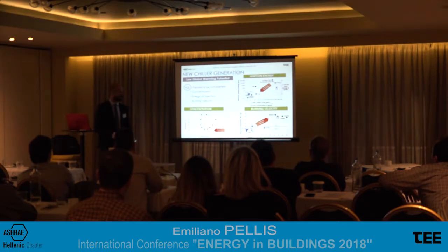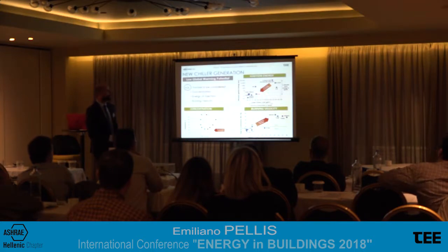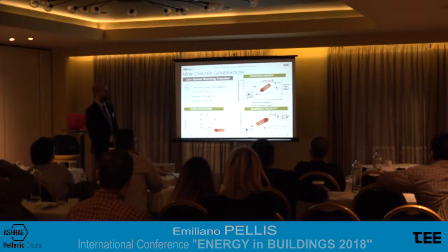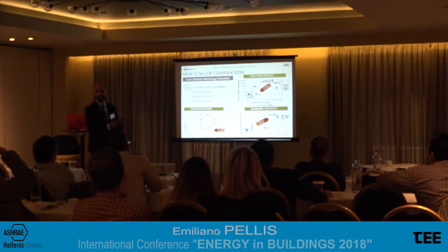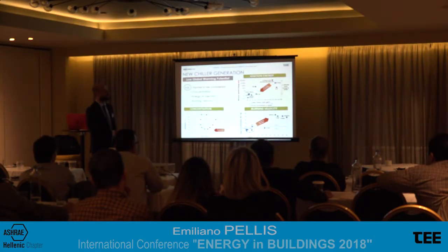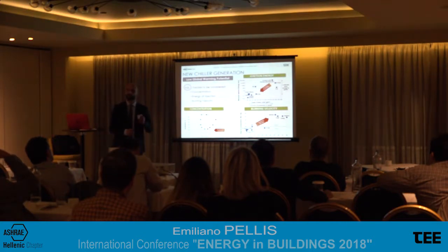When we talk about A2L class refrigerant, they are flammable only within a concentration range. Outside of this area, they are not flammable, exactly similar to A1 refrigerant. Second point, ignition energy. To ignite the refrigerant, we need some energy. If you look at the graph here, on the horizontal axis you have the ignition energy needed, and on the vertical axis here we have the ignition energy for the gasoline, which is something that all of us can easily identify as flammable. If we take one of the new refrigerants, for example this one, you see the ignition energy is definitely higher, more than 250,000 times. Practically it means that the flame ignition is more difficult for A2L refrigerant.